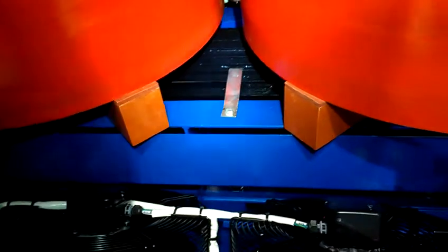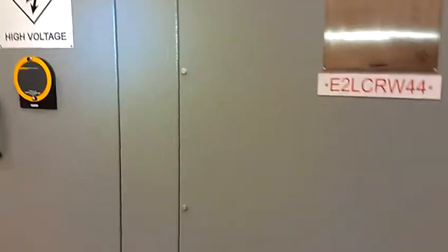This is the core, grounded here with the core strap. These are IR windows — six per transformer.